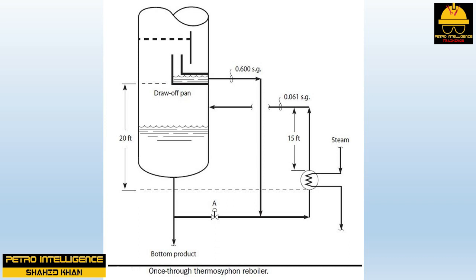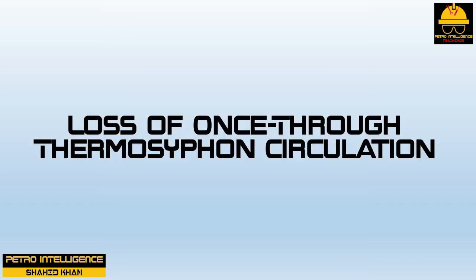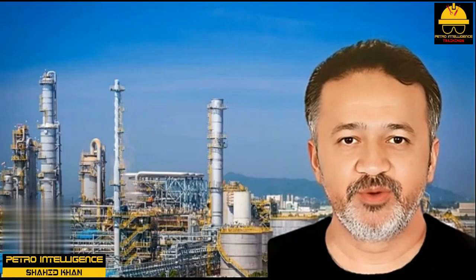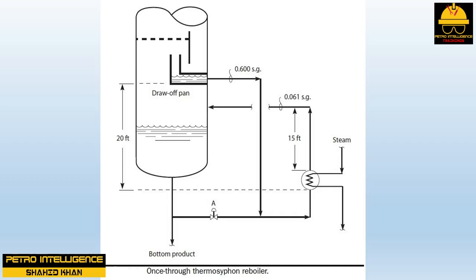The once-through thermosyphon reboiler operates as follows: all the liquid from the bottom tray flows to the reboiler; none of the liquid from the bottom of the tower flows to the reboiler. All the bottoms product comes from the liquid portion of the reboiler effluent. This means that when the once-through thermosyphon reboiler is working correctly, the reboiler outlet temperature and the tower bottom temperature are identical. If the tower bottom temperature is cooler than the reboiler outlet temperature, something has gone wrong with the thermosyphon circulation.